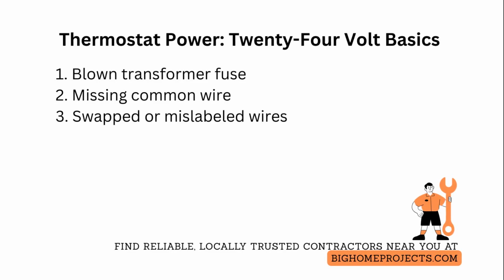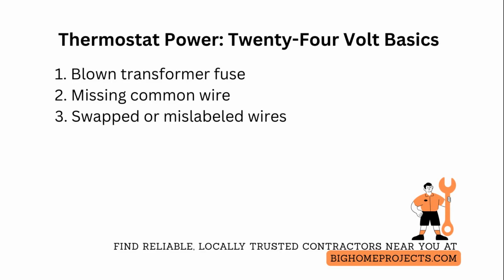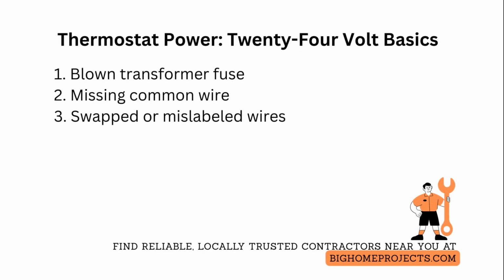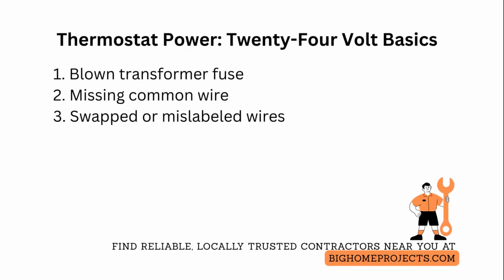One of the frequent wiring mistakes is swapped R and C or mislabeling wires during replacement, causing short cycles and equipment damage. Prevent this by labeling wires, testing continuity, and verifying R to C voltage before finalizing the install.